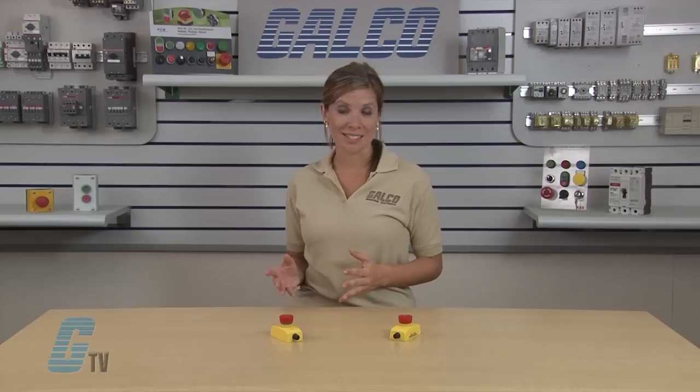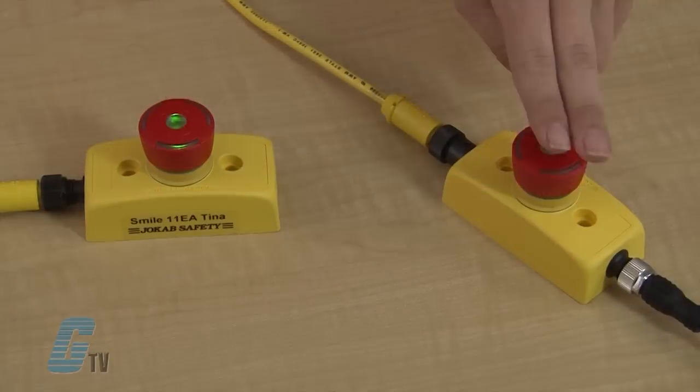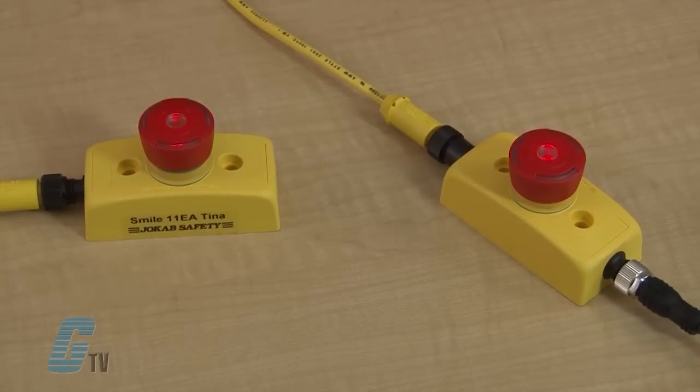ABB Jokab Safety also has Smile TINA emergency stops that are often used with dynamic safety circuits, fulfilling safety category 4. The Smile TINA has similar LED indicating lights with an additional feature of a flashing red and green light to indicate that an e-stop earlier in the circuit has been pressed.